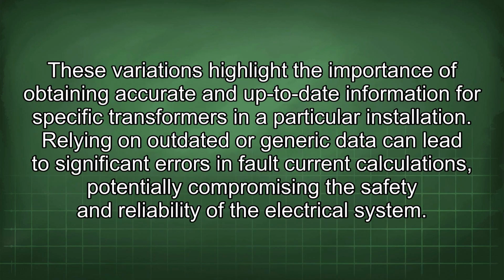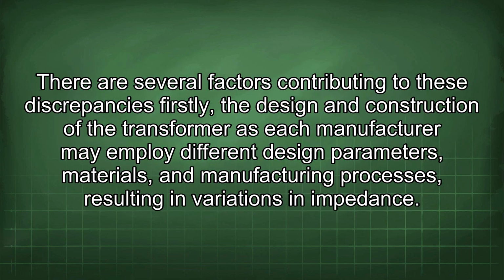These variations highlight the importance of obtaining accurate and up-to-date information for specific transformers in a particular installation. Relying on outdated or generic data can lead to significant errors in fault current calculations, potentially compromising the safety and reliability of the electrical system. There are several factors contributing to these discrepancies. Firstly, the design and construction of the transformer, as each manufacturer may employ different design parameters, materials, and manufacturing processes, resulting in variations in impedance.